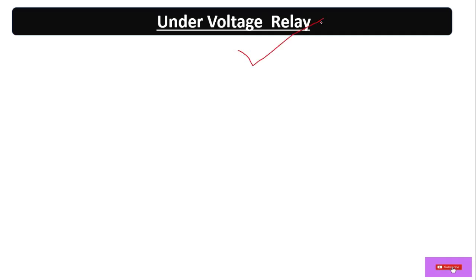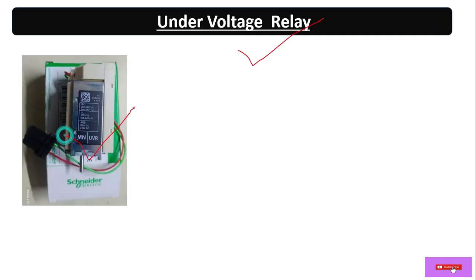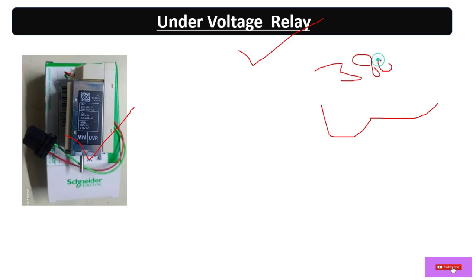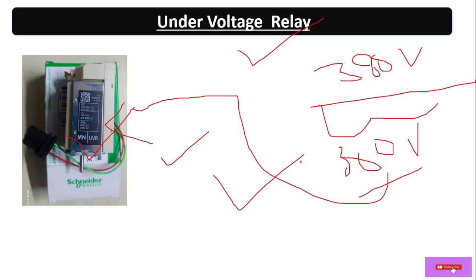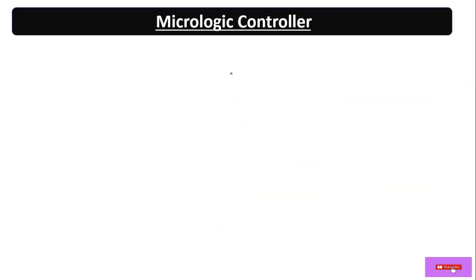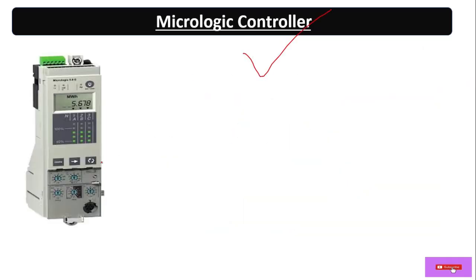The undervoltage relay protects from undervoltage. Suppose we have set it to 380 volts — if the voltage goes below that, say 360 volts, under that condition this relay will activate and it will trip the circuit.